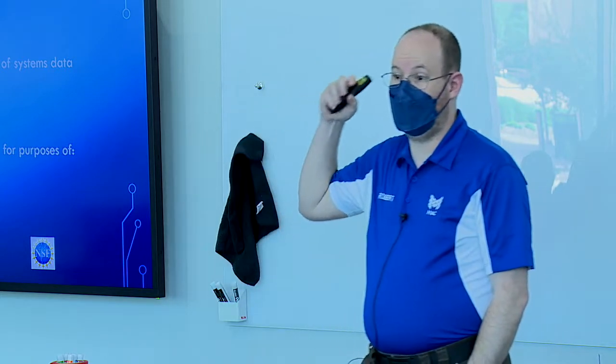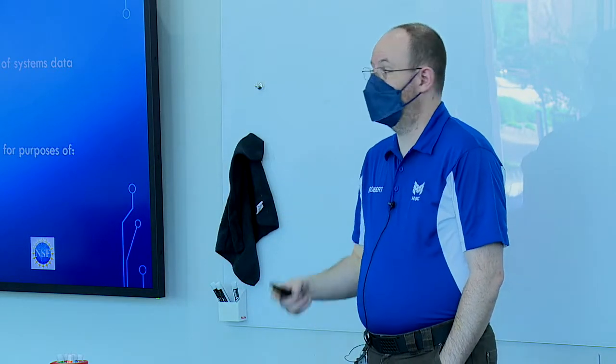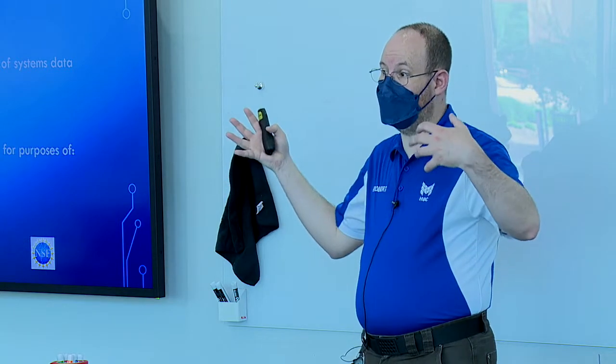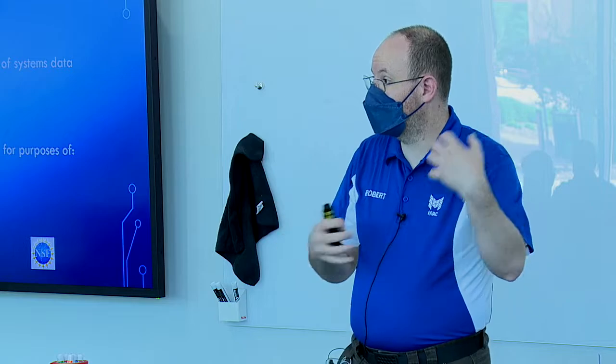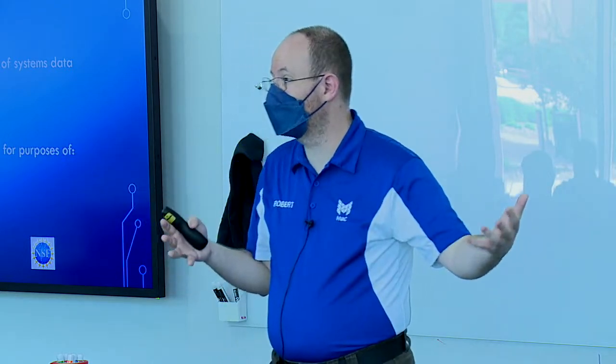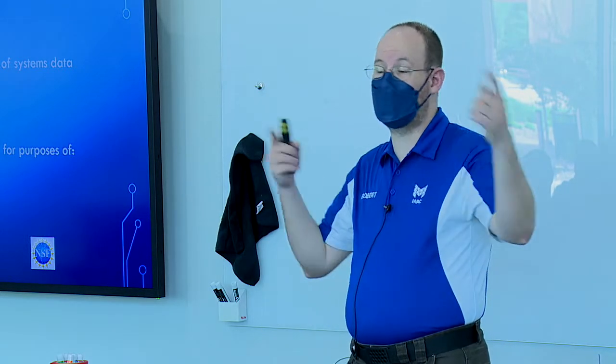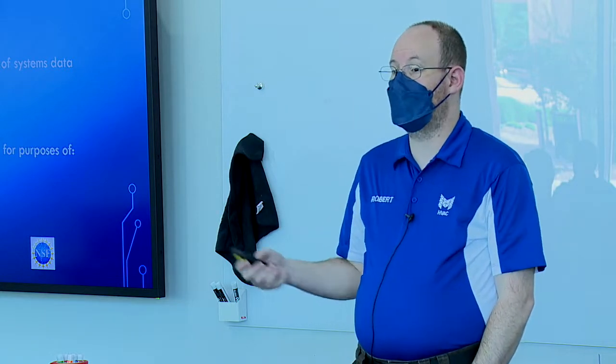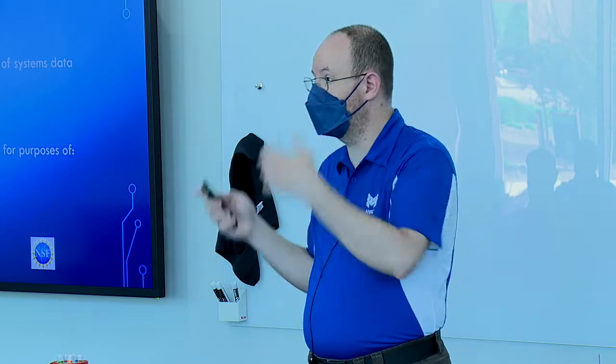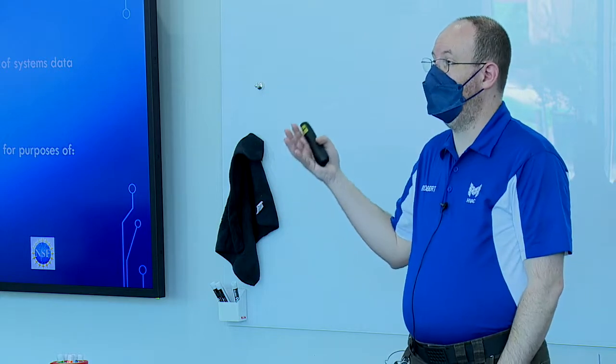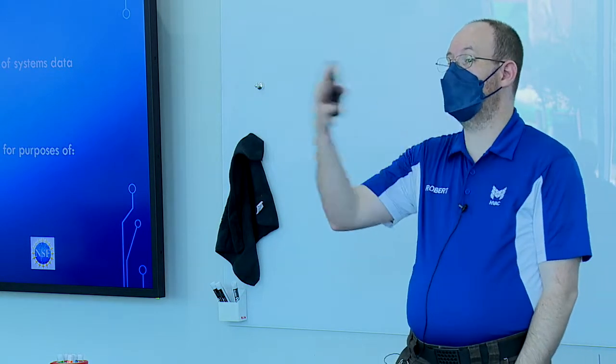If you're recording, again, back to that electrical meter data, that's not something that you're typically going to use in the system unless you're dealing with demand or time of use type stuff. But it is something that's probably going to be useful to report to people on a monthly basis. Maybe you're just comparing it to the data that you're getting from the utility. Maybe you're using it to plan for various things. Maybe you're using it to verify your return on investment for an energy upgrade being done, or that was done. Reporting that out on a periodic basis is a common tool within most control systems.